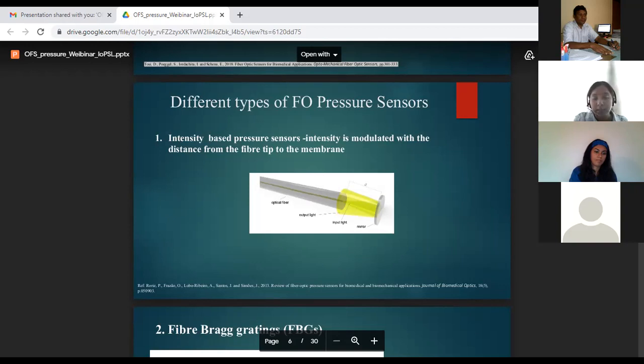So the intensity of the light coming out from the fiber, the reflected light, can depend on various parameters like the core diameter and the position of the fiber, as well as the numerical aperture. But it also directly depends on the distance between the fiber tip and the membrane. So the light intensity increases rapidly from zero when the diaphragm is in contact with the fiber end plane, and then it reaches a maximum when the diaphragm plane matches the position where the solid angles of these two numerical apertures intersect most, as you can see in this picture.